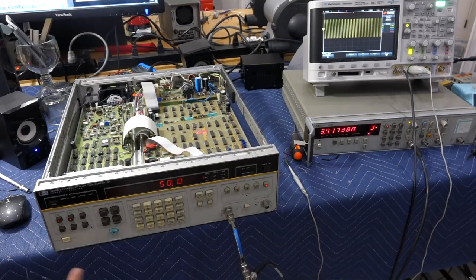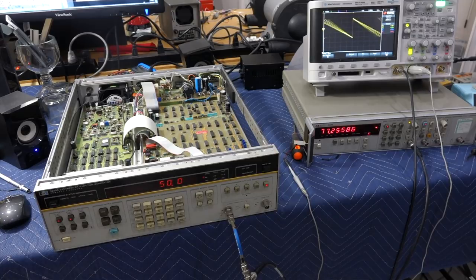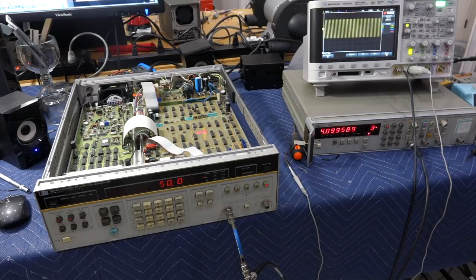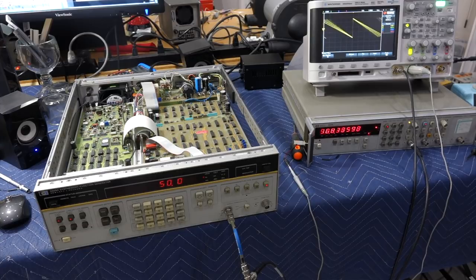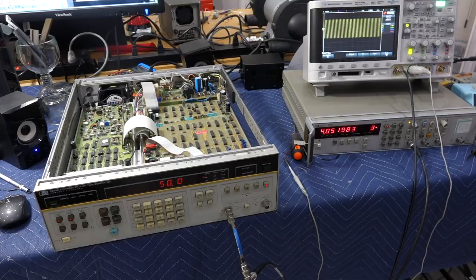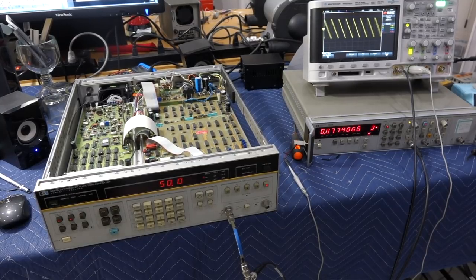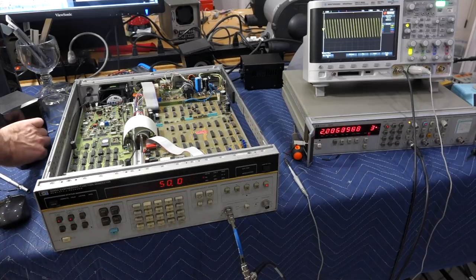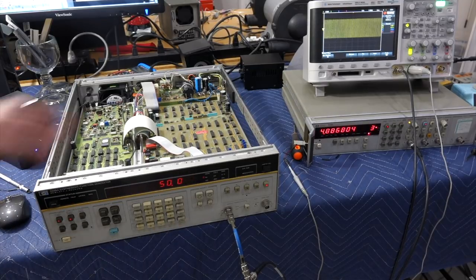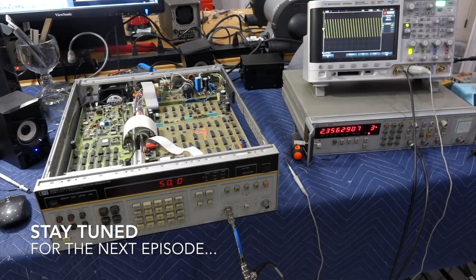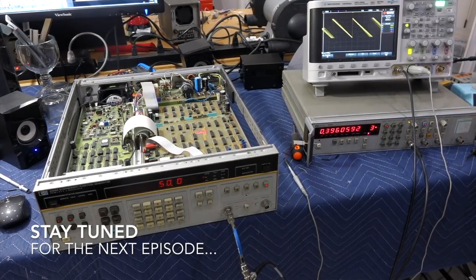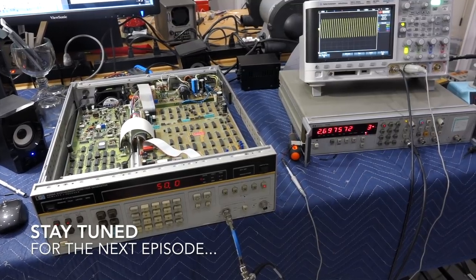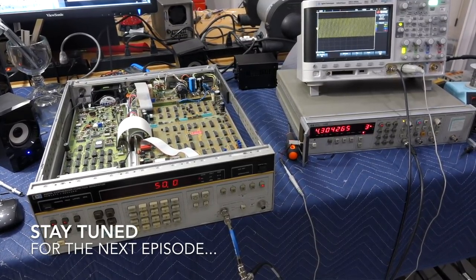And this is the A model. It doesn't have the internal modulation, unfortunately. Because the B model has internal modulation including arbitrary memory. Right, but this has external modulation. This one is external. Well, I've just got another function here. Yeah, I just need to repair the next one. I have another one actually. There you go. So I'm happy I repaired this one. And it will make the recap people happy, because the only thing that was wrong with it is that cap. All right, well you recappers be happy, that's what this instrument needed. But just one cap.